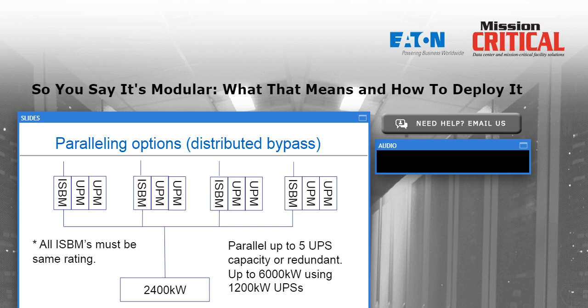Steve asks, is there a point where you can no longer add modules, or are you only restricted by the space you have? That's a very good question, and the answer is yes. Almost always the restriction has to do with the available power in the premises wiring in the building. So in other words, if I put in a megawatt's worth of building wiring, then the UPS that's connected there should not get any bigger than 1 megawatt.